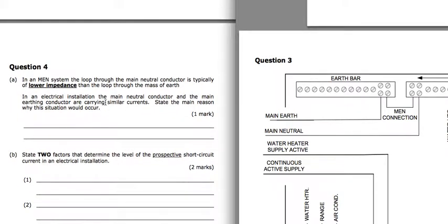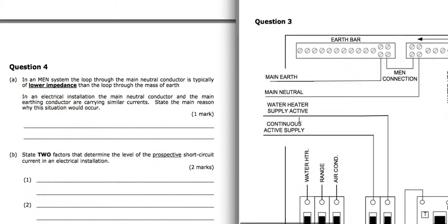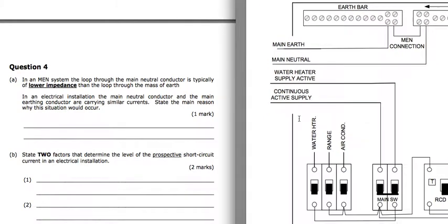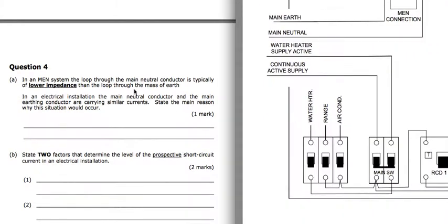Question 4. The MEN system, the loop through the main neutral conductor is typically of a lower impedance than the loop through the mass of Earth. Basically because this Earth neutral conductor is a solid copper, or it's a copper conductor, it's a continuous connection, whereas through the mass of Earth we're relying on the resistance of the Earth, the moisture in the Earth, to give us a low impedance, and typically that's not going to be as low as a permanently connected conductor.